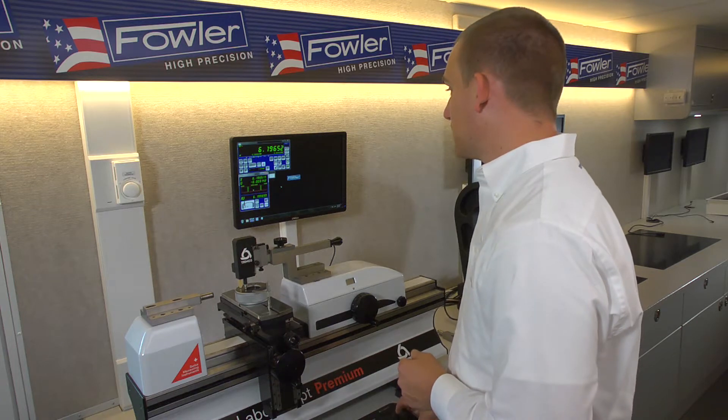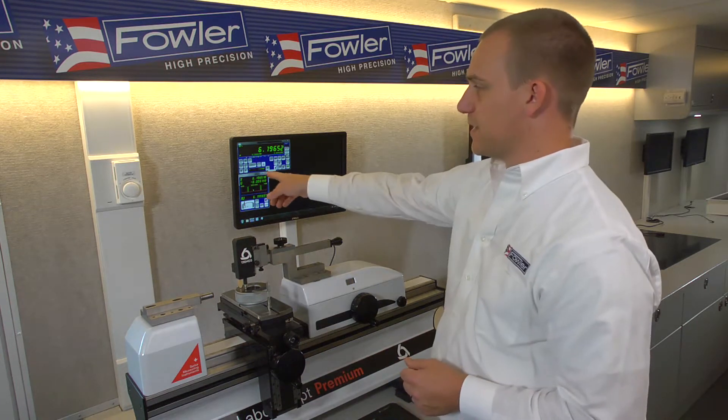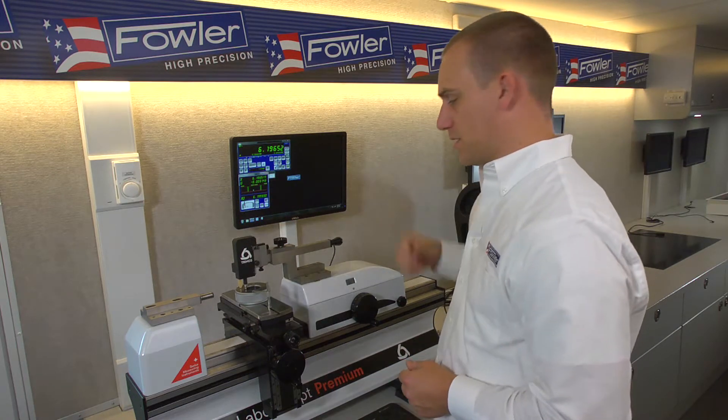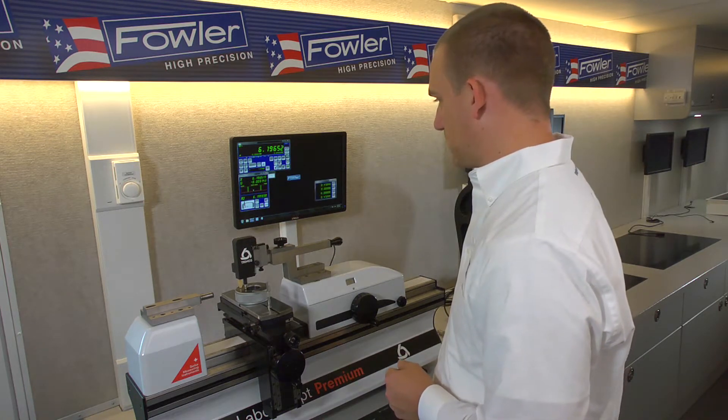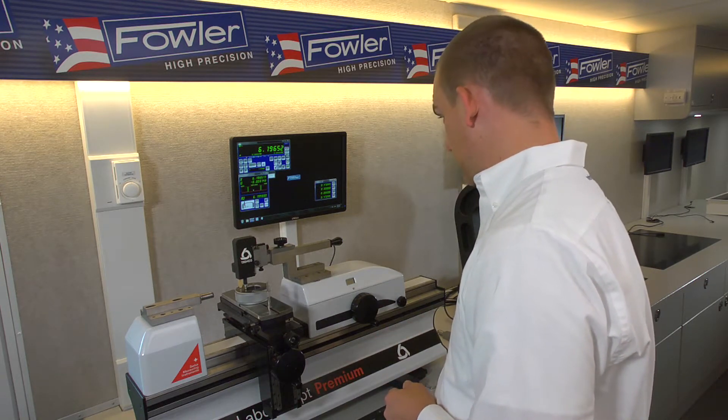Now what we can do is press this question mark here. So with the dynamic internal measurement window open, the question mark becomes a wizard for setting the probe constant.